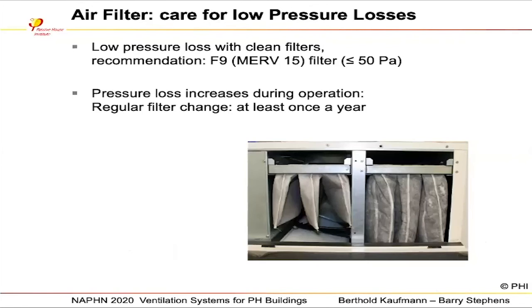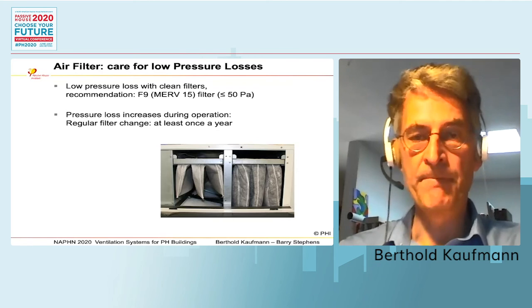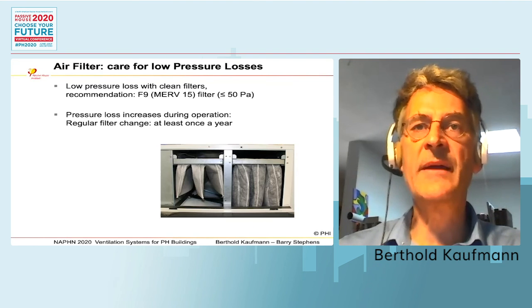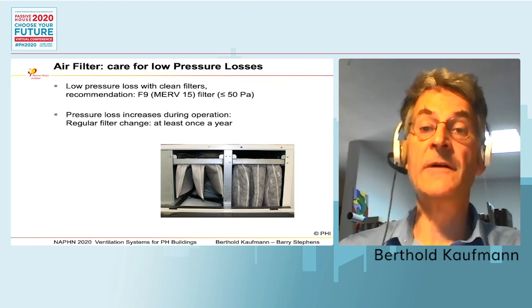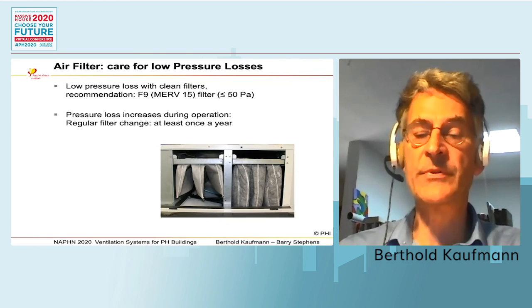Next point is air filters. Please provide filters with low pressure losses, and this means a large surface area available for the air going through. The bag filters in the pictures are the best example of this. The longer the bag is, the better. You can have these bags in a very small space, and the pressure losses will be quite low for a long time. So spend a little more money on the better filters, and it will be paid back later because of lower operation cost.